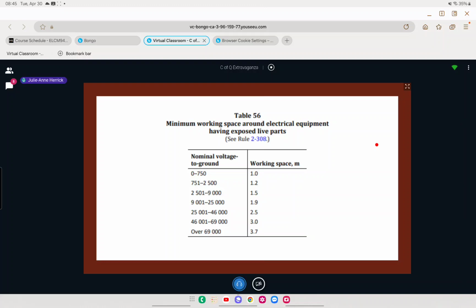In section A, the safety section, if you are going to get a code question, I can almost guarantee it's going to be based off of this table - minimum working space around electrical equipment having exposed parts. So when you're in section A of the C of Q, this is probably the table you're going to have.